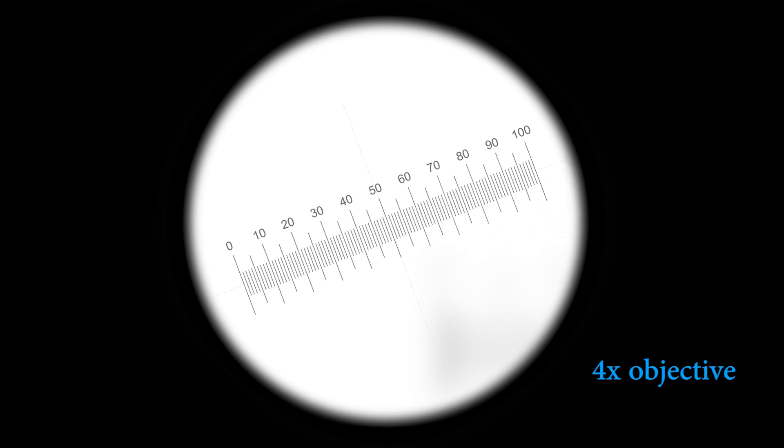The size of an object in ocular units changes depending on zoom level, so we'll have to calibrate for each power level we'll be using.